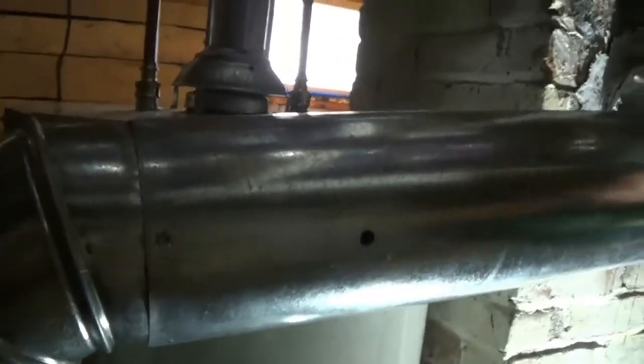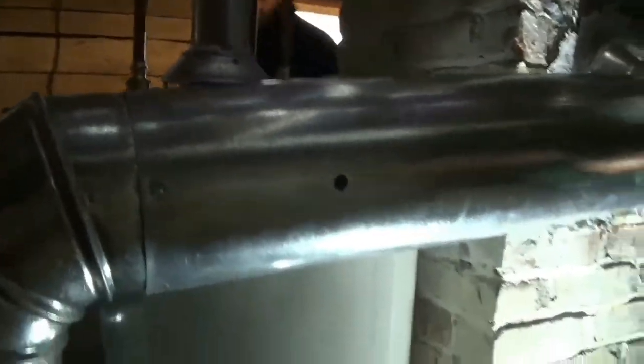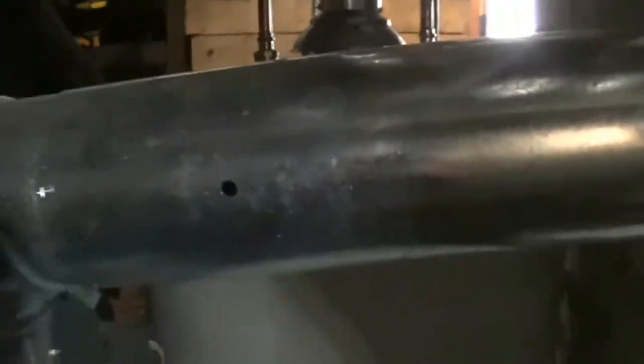The boiler has a box on the back of it that is the start of this flue pipe here, and this box is what we would call the draft hood for this boiler. So I'm going to be testing the carbon monoxide by pushing my probe up inside here before air mixes in, and then I'm also going to test for spillage right at this draft hood opening, and then I'm going to test for draft right here after the elbow of that atmospheric steam boiler. So I'm going to put my light here so we can see what's going on back here eventually.